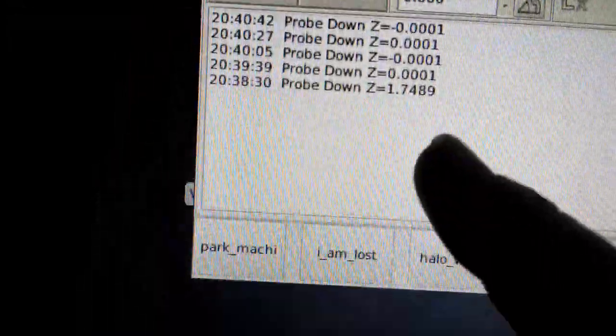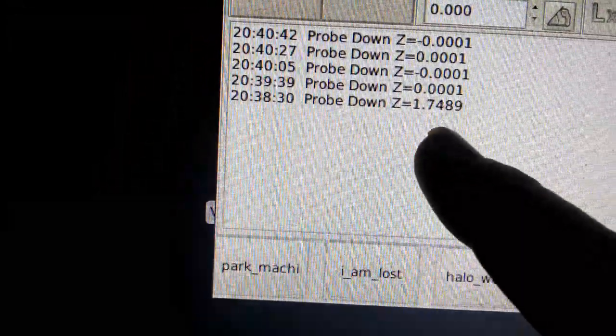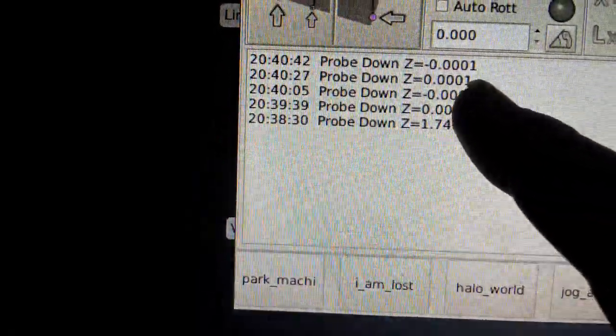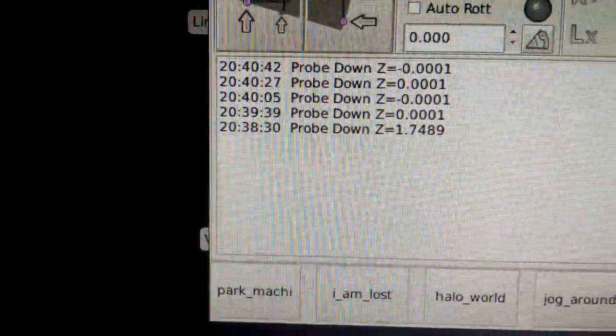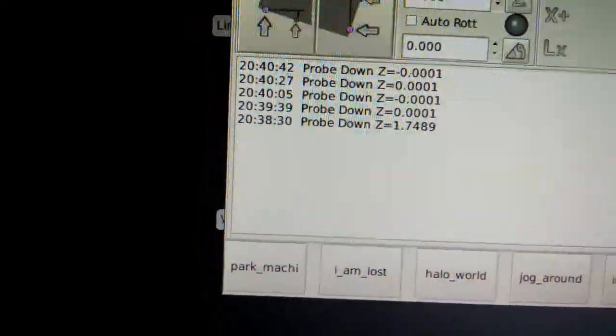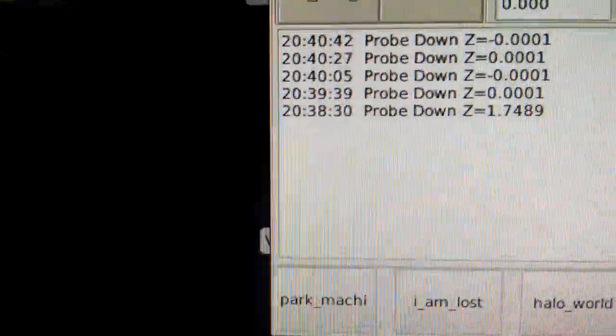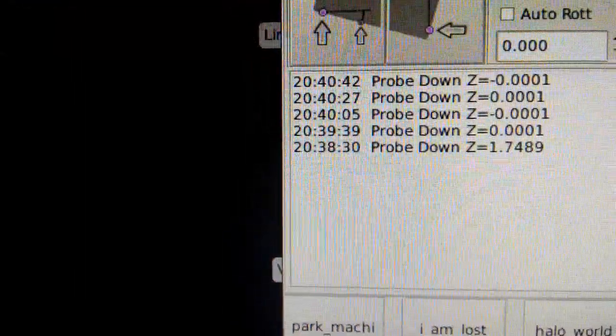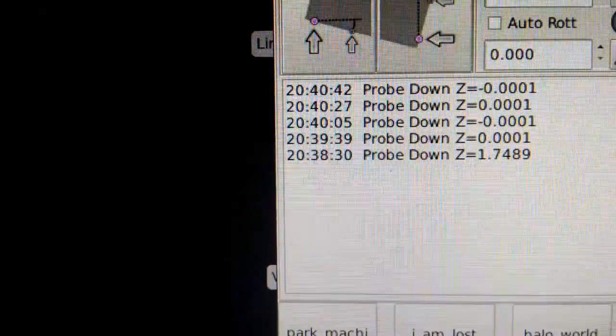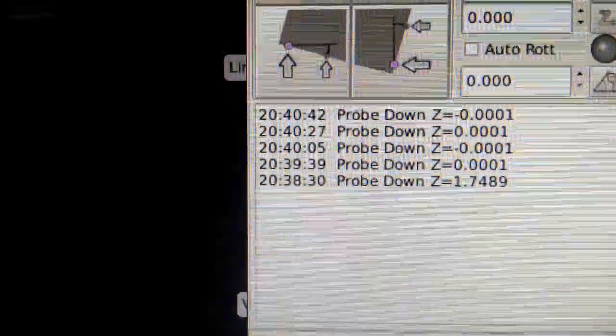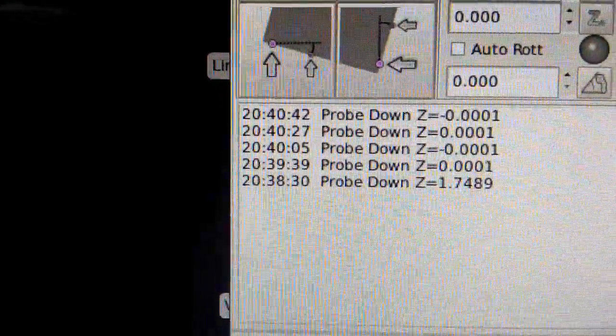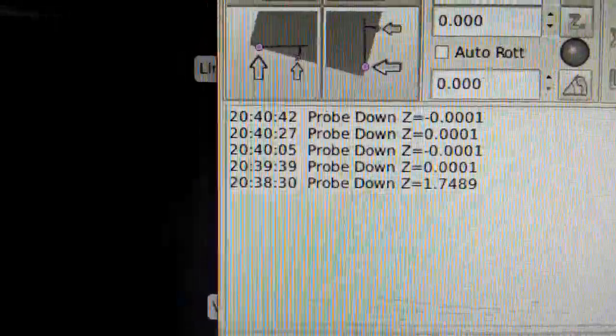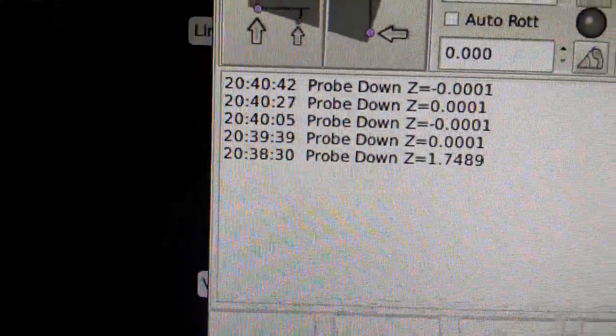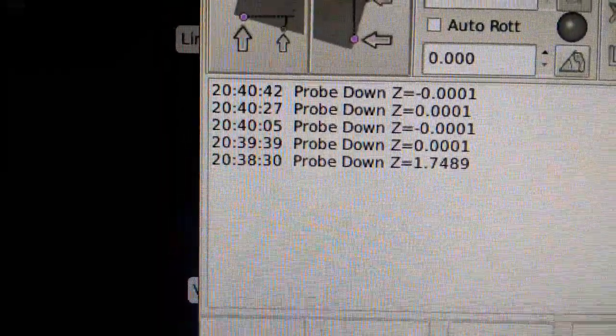then on the subsequent probes I turned auto 0 off, and it said that it probed down, and the first time it was plus 1/10,000th, second time minus 1/10,000th, third time plus 1, fourth time minus 1. So within those 2 minutes, 3 minutes, and 5 different probes, we were within one plus or minus 1/10,000ths of 0 with the same exact position. So everything should be pretty close.